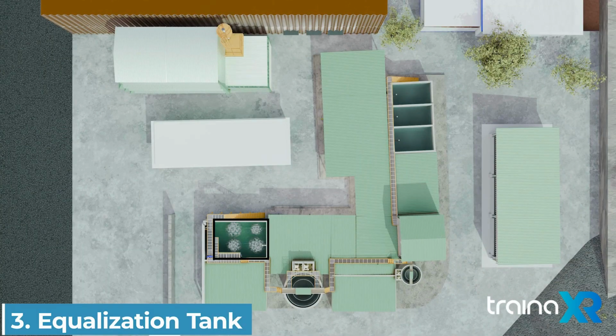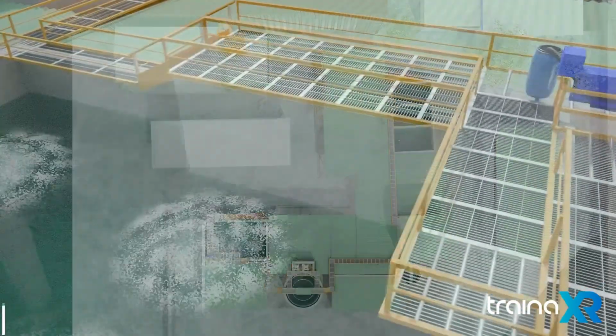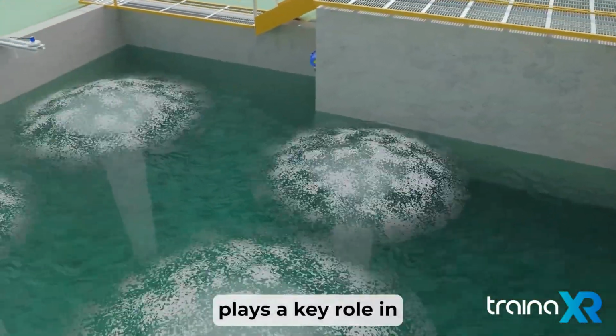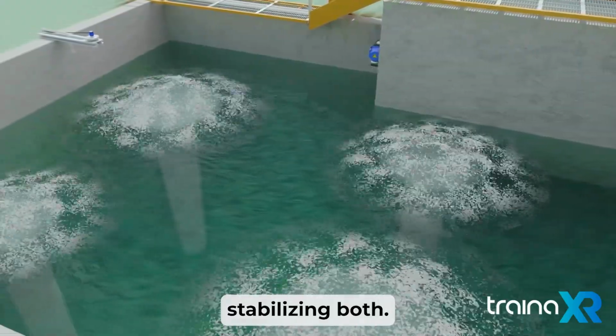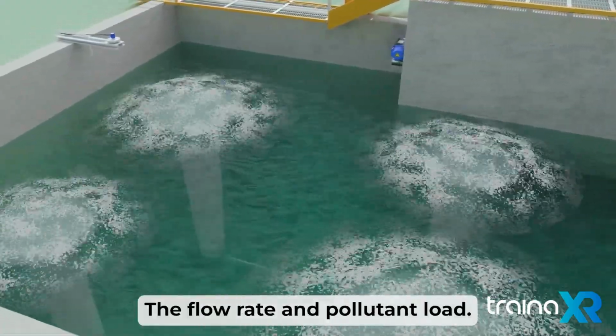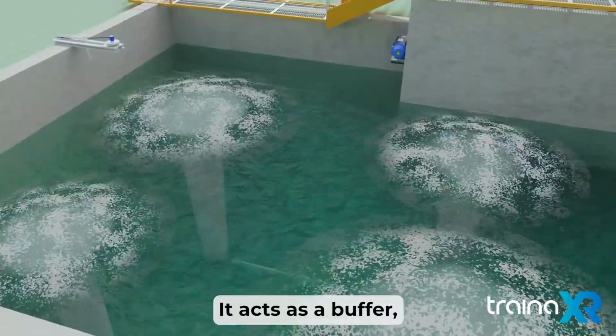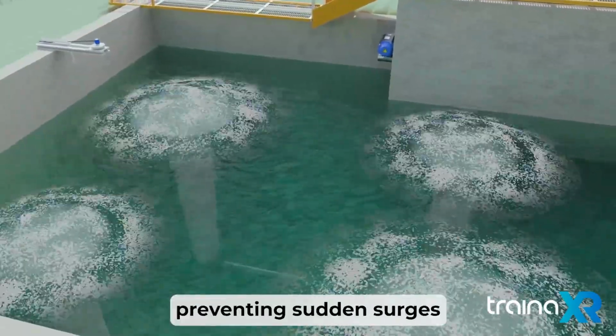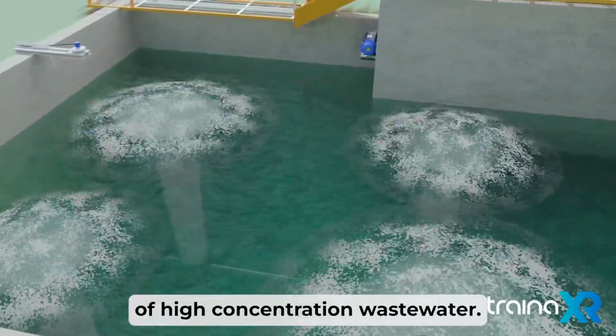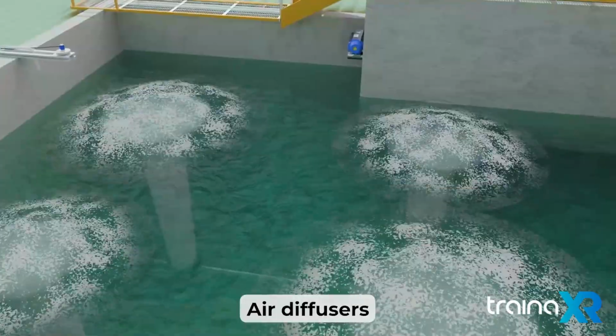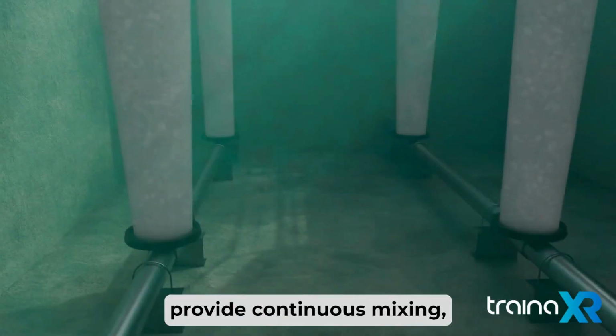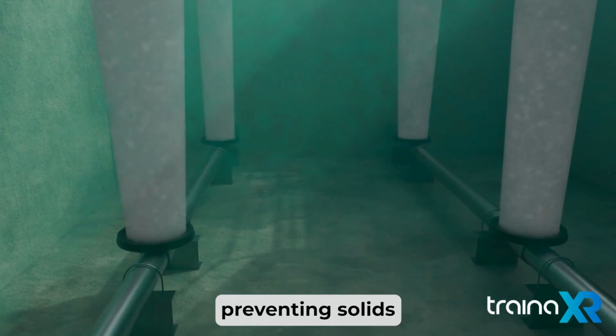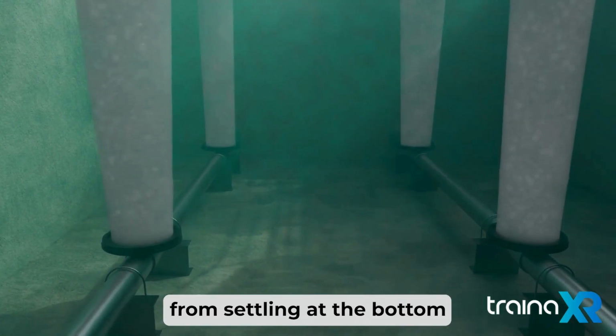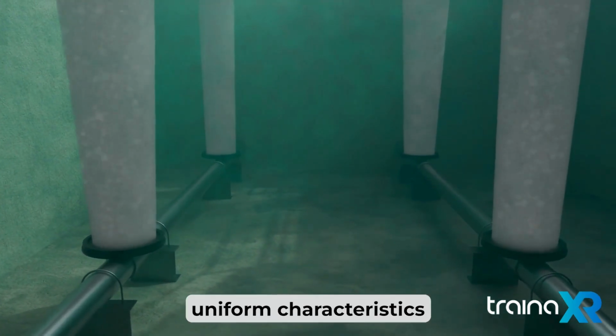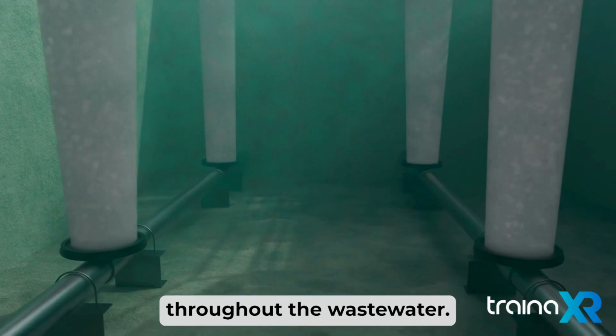Equalization tank. The equalization tank plays a key role in stabilizing both the flow rate and pollutant load. It acts as a buffer, preventing sudden surges of high-concentration wastewater. Air diffusers installed in the tank provide continuous mixing, preventing solids from settling at the bottom and maintaining uniform characteristics throughout the wastewater.